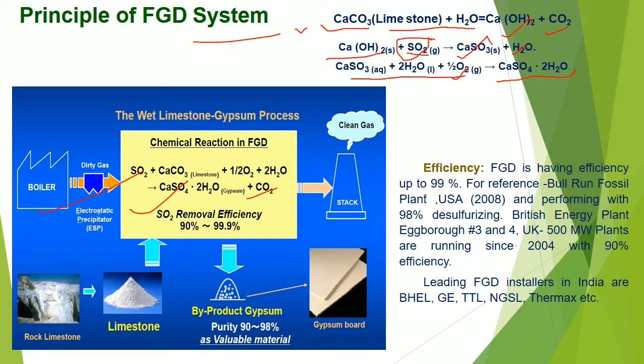FGD has efficiency up to 99%. For reference, the Bull Run fossil plant, a 920 MW coal-based plant in USA, started its operation with FGD in 2008 and is performing with 98% desulphurization. British Energy plant, Eggborough, units 3 and 4 in UK, also 500 MW plants, running since 2004 with 90% efficiency. Efficiency depends on the nature and quality of fuel and sulfur content. Leading FGD installers in India are BHEL, GE, TTL, NGSL, Thermax, etc.